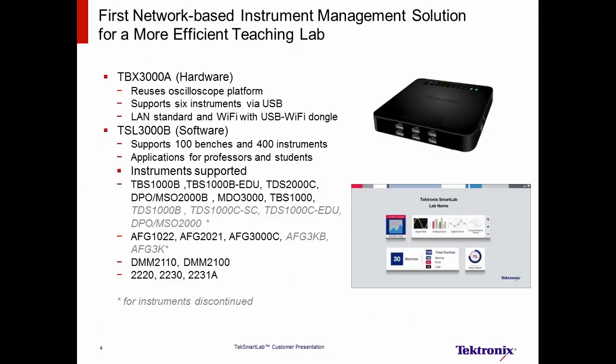The TekSmartLab consists of 2 new products. The hardware. The TBX3000A utilizes the same interface found on Tektronix oscilloscopes. It can support a maximum of 6 instruments via USB cables and can connect with a network with a standard LAN port or with Wi-Fi when equipped with the optional USB Wi-Fi dongle.